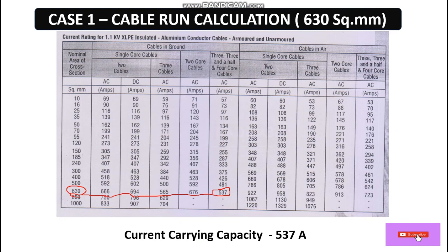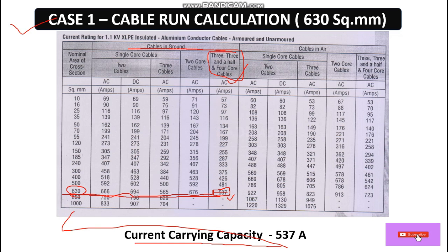Now let's calculate the cable run. Here we are going to install the cable underground. Considering we are going to lay the cable underground, we look at the 3.5 or 4 core options. The formula for the number of cable runs is: Number of cable runs = Full load current / (Current carrying capacity × Derating factor). The derating factor depends on whether the cable is laid underground or in air.